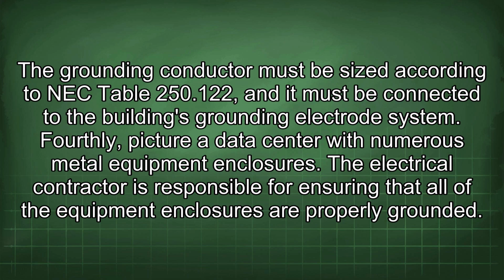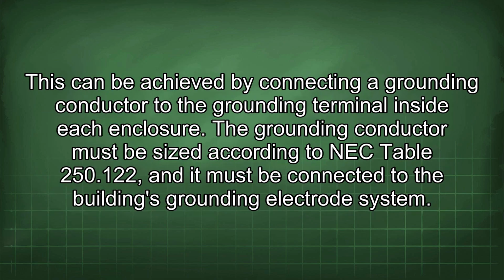Fourthly, picture a data center with numerous metal equipment enclosures. The electrical contractor is responsible for ensuring that all of the equipment enclosures are properly grounded. This can be achieved by connecting a grounding conductor to the grounding terminal inside each enclosure. The grounding conductor must be sized according to NEC Table 250.122, and it must be connected to the building's grounding electrode system.